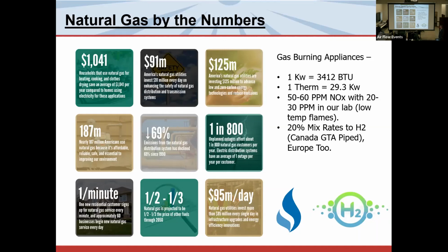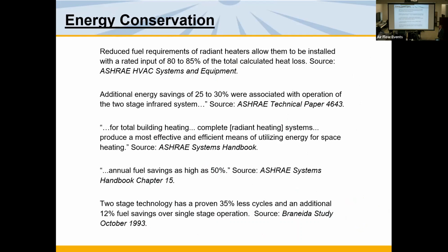Next slide, please. So what does this mean? In my opinion, energy conservation. It's telling my kids to go down the basement, turn off the lights, okay? It's trying not to use more energy than you need. And this is really what infrared heaters are known for, okay? We have all kinds of studies and facts and figures. They're in the ASHRAE Fundamentals Handbook, which basically states a 20 to 30, sometimes 40% fuel savings. The more the air changes, the higher the building, the more we can, with infrared heating systems, impact the overall energy consumption and energy conservation. So we can burn less gas and we can effectively heat a big space. Next slide, please.